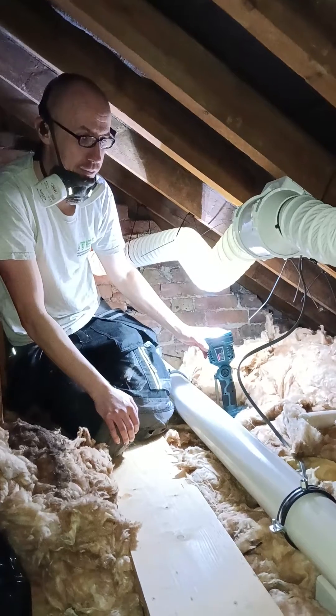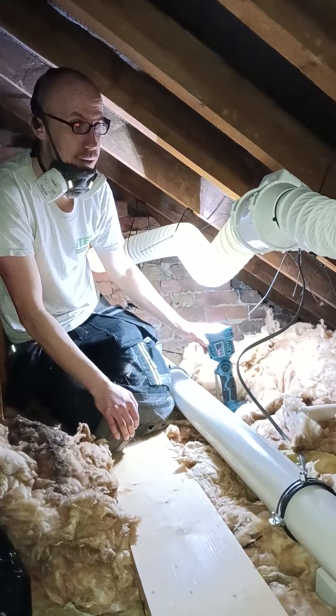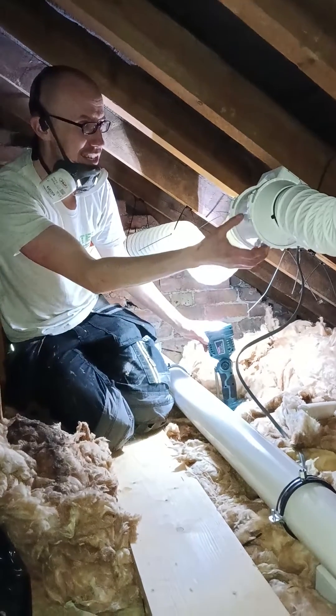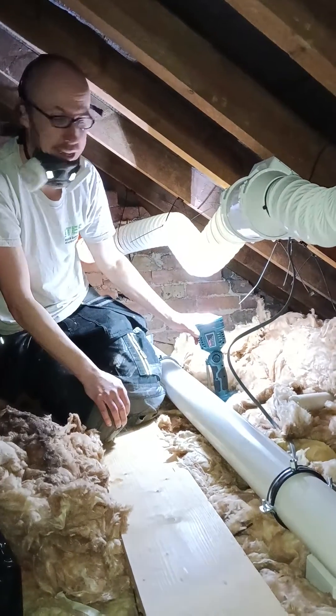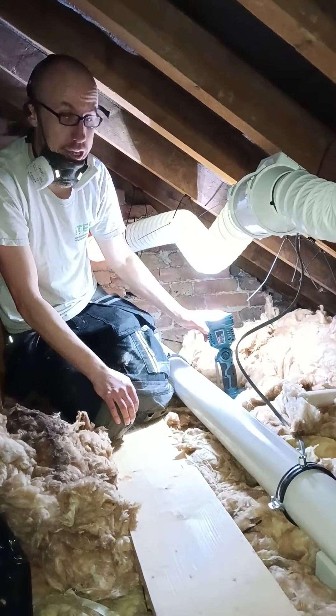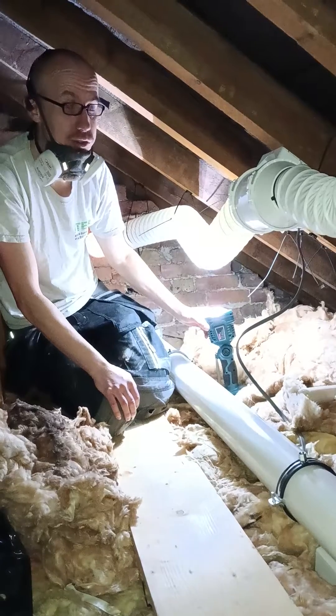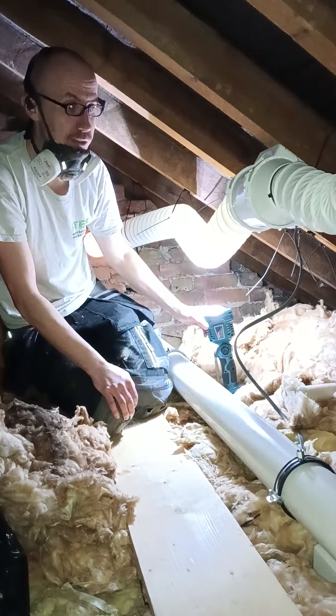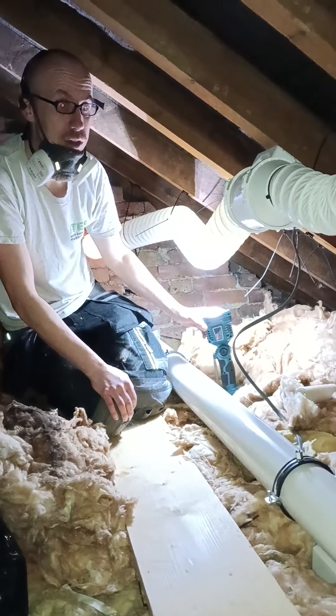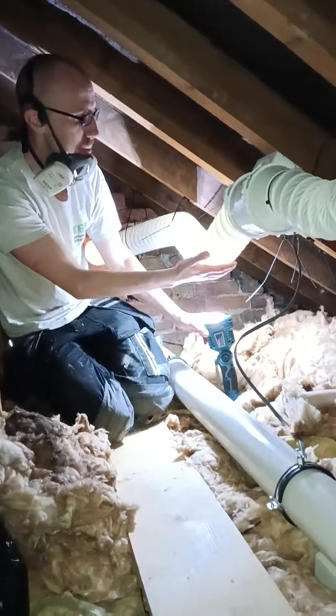These are the little design errors we're going to combat today. Looking down in the bathroom, this family is really suffering from condensation — you can really tell. I don't think this fan is quite up to the job by itself, so we're going to reuse it and couple it with our super-duper whoppers, so there's two of them trying to draw air. We're going to give them a master switch for over the winter months — they can switch it on throughout winter and leave it on until it starts getting warmer and they can start opening windows.